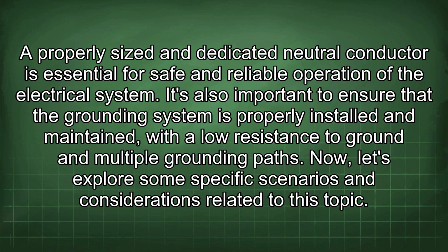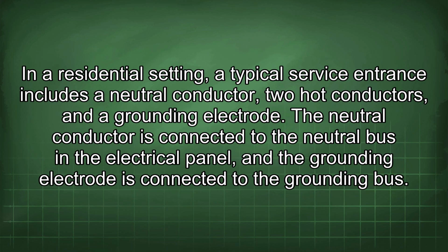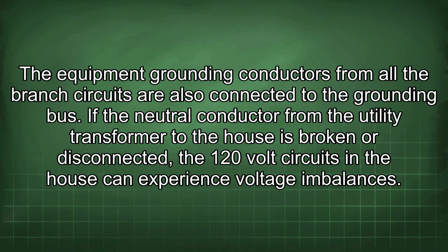It's also important to ensure that the grounding system is properly installed and maintained, with a low resistance to ground and multiple grounding paths. Now, let's explore some specific scenarios and considerations related to this topic. In a residential setting, a typical service entrance includes a neutral conductor, 2 hot conductors, and a grounding electrode. The neutral conductor is connected to the neutral bus in the electrical panel, and the grounding electrode is connected to the grounding bus. The equipment grounding conductors from all the branch circuits are also connected to the grounding bus.